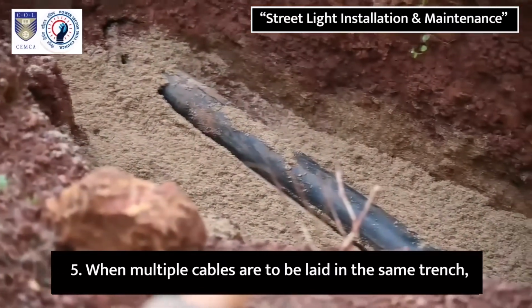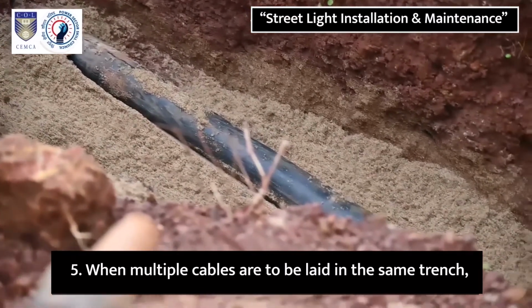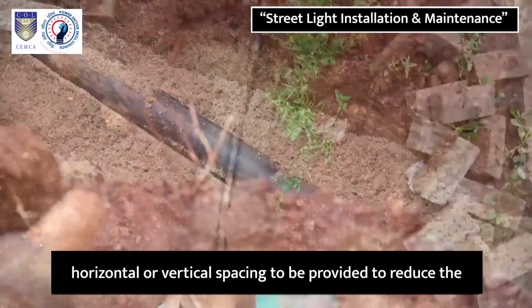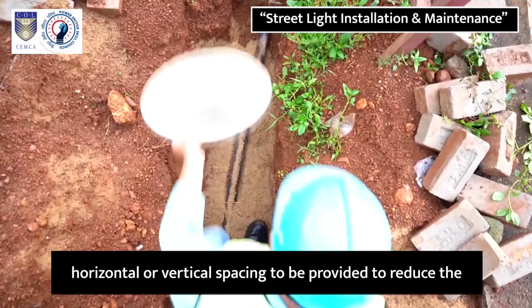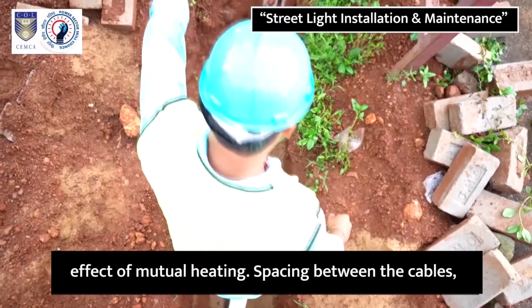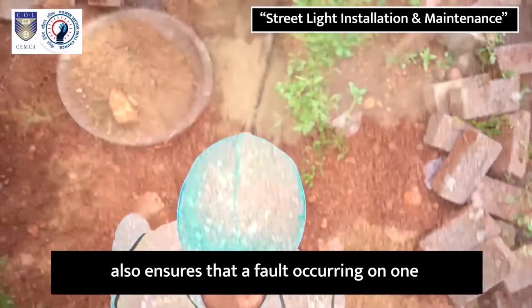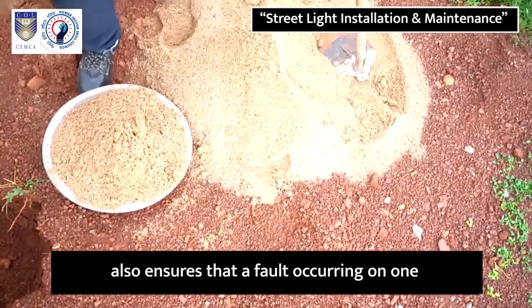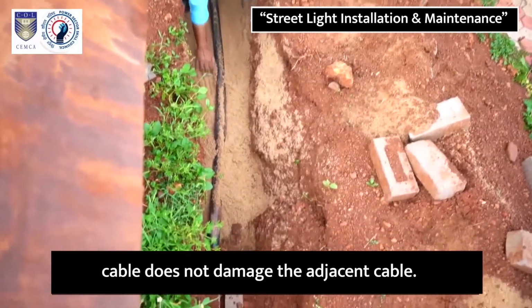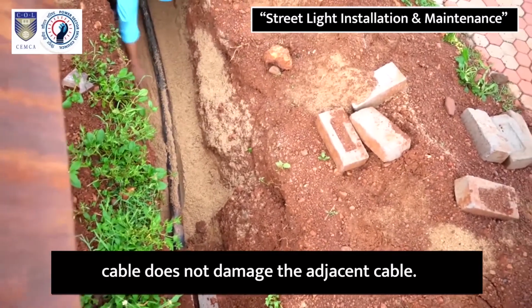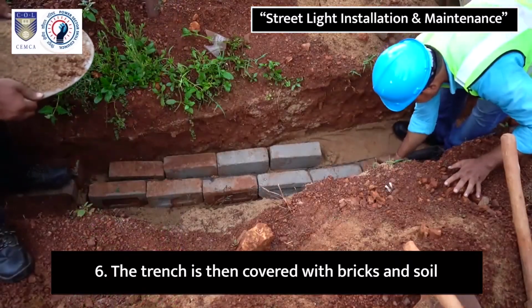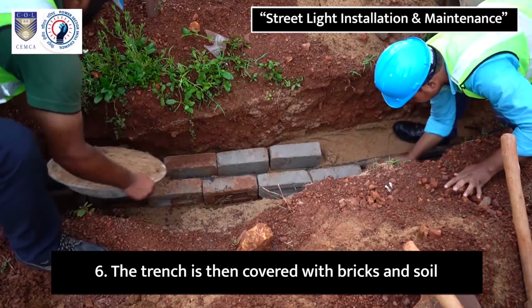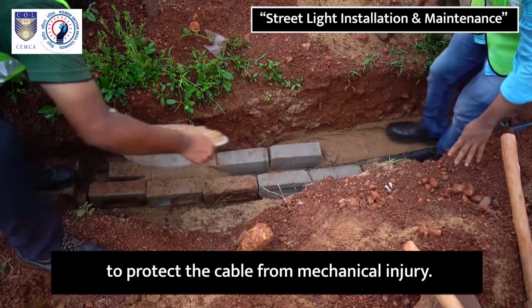5. When multiple cables are to be laid in the same trench, horizontal or vertical spacing to be provided to reduce the effect of mutual heating. Spacing between the cables also ensures that a fault occurring on one cable does not damage the adjacent cable. 6. The trench is then covered with bricks and soil to protect the cable from mechanical injury.